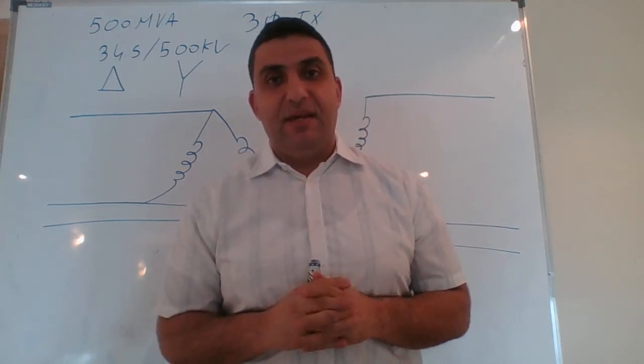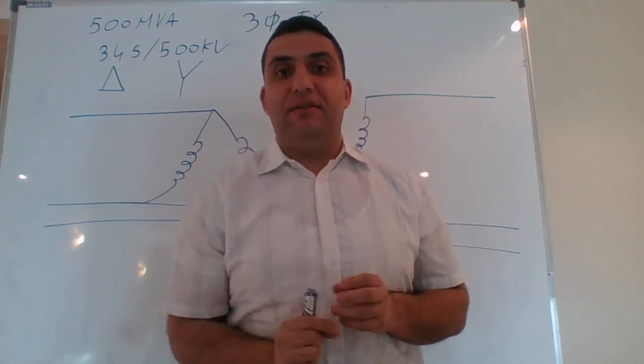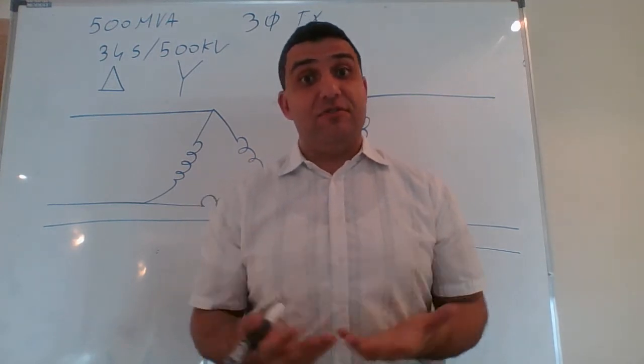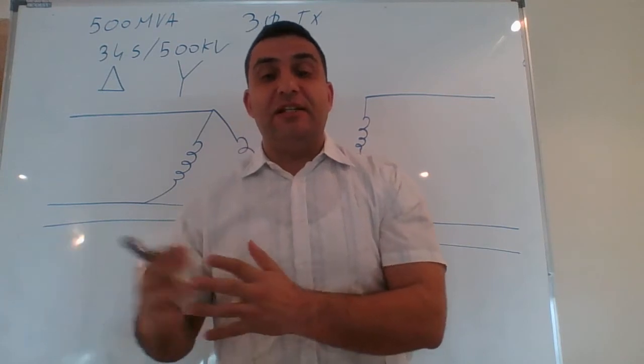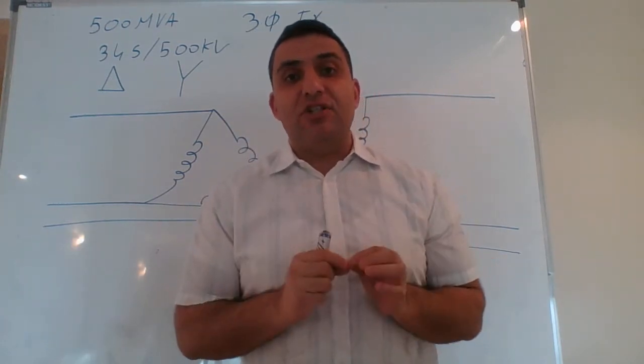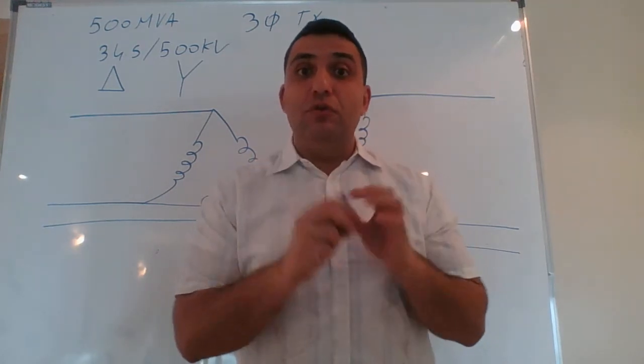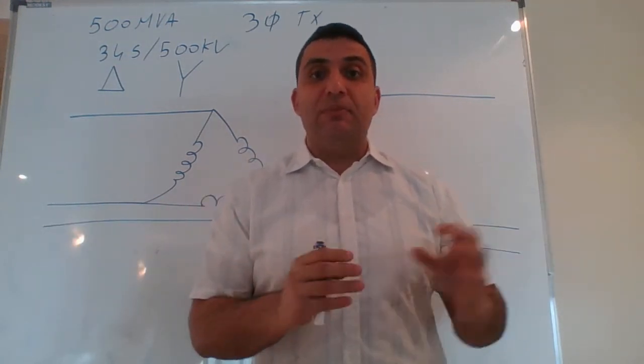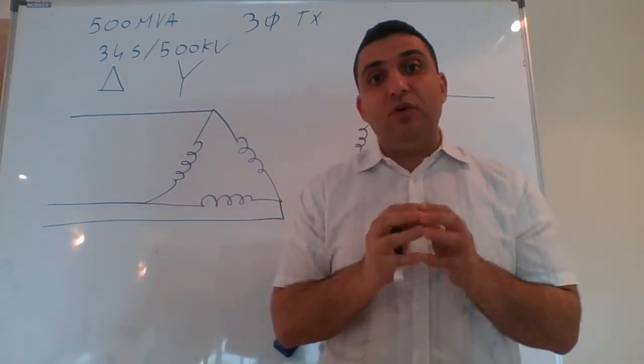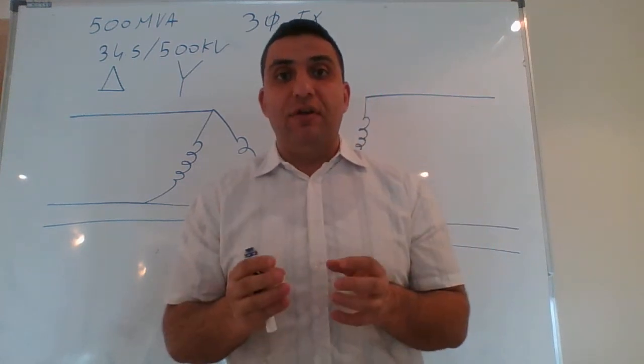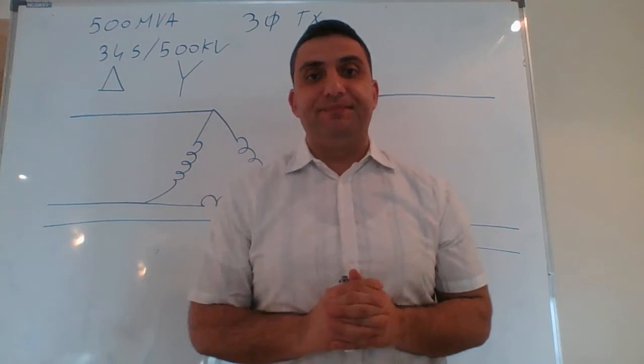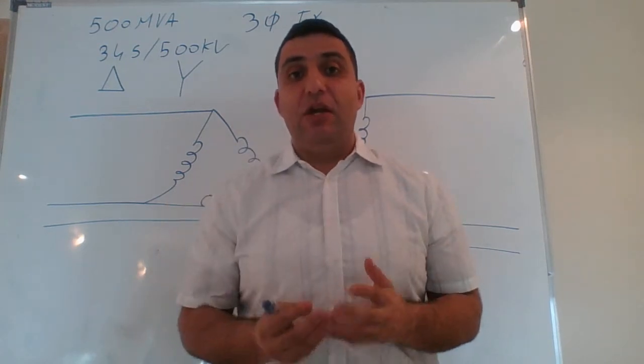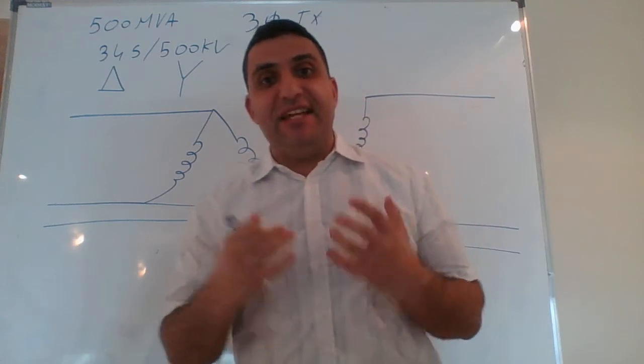Before we go into the three-phase differential protection, I want to highlight one element regarding the inrush current. If we are going to energize a single-phase transformer without the secondary side connected to any load, I will have an inrush current. The inrush current occurs because the magnetic field goes into saturation. When the magnetic field goes into saturation, the current magnitude on the primary side will go up, depending on the magnetizing curve of the system.